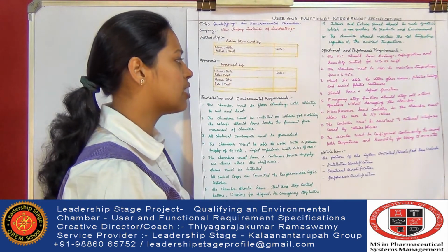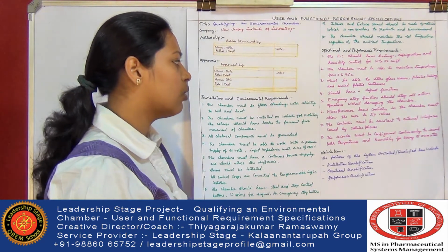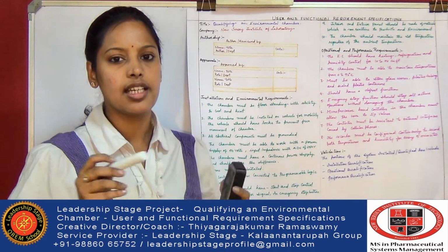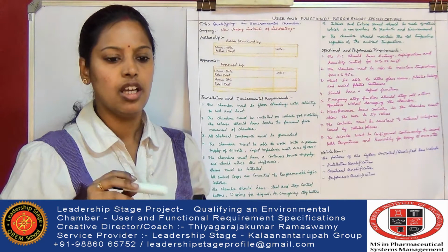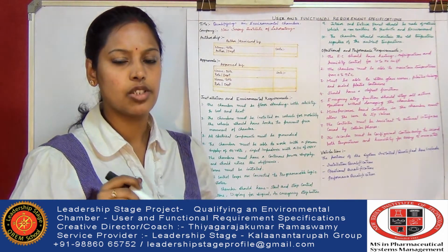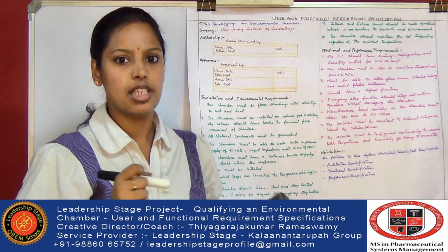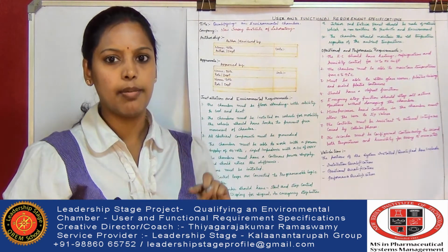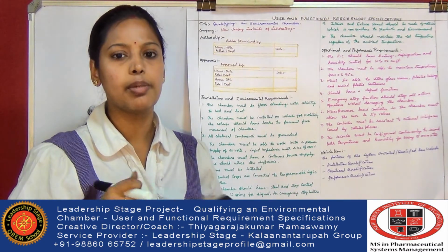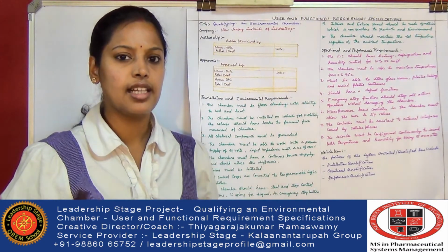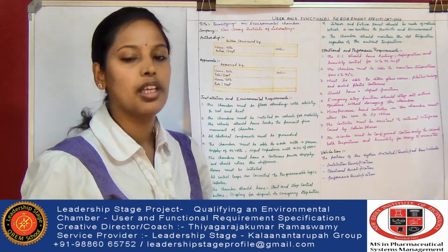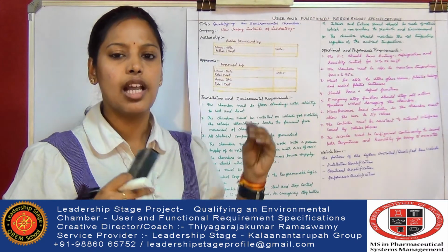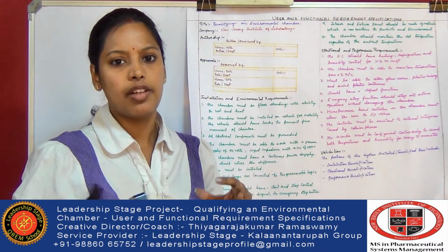The microprocessor based controller in the chamber will allow the user to input values. When you run the processor, it should have long-term values, and it must be able to store them, as we see in PCR, polymerase chain reaction. When we press the step button or the back button, it will repeat the process, like a redial thing. So it should be microprocessor based control. The advantage is that it will help us remember what we have done in the previous cycle.